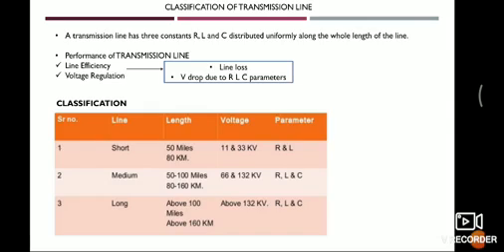Classification is three ways: short, medium, and long. Short transmission line is up to 80 km or 50 miles, with voltage of 11 to 33 kV. For short transmission lines, only resistance and inductance parameters are considered — capacitance is neglected. Medium is 80 to 160 km, and long is above 160 km. For medium and long lines, resistance, inductance, and capacitance are all considered. In this chapter, we will only discuss the short transmission line.